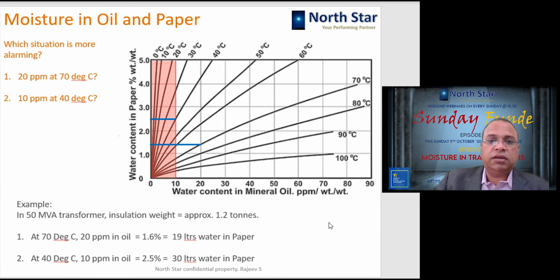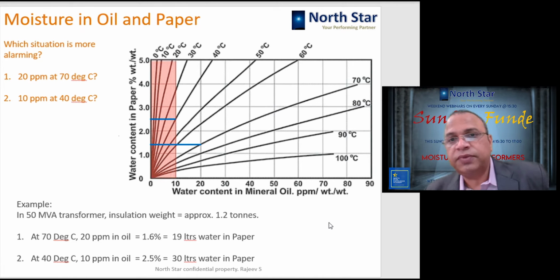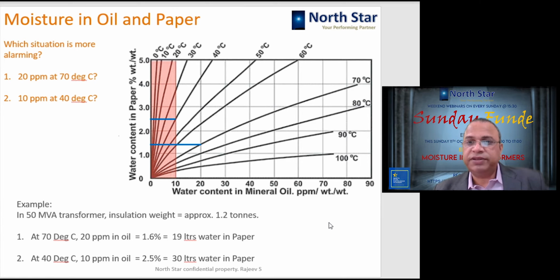Now let us look more into the equilibrium of moisture in the oil. Here you can see several graph lines at different temperatures. These are the temperatures of that particular transformer, from 0 degrees to 10, 20, 30, 40, 60, 70. Here it is the water content in mineral oil in ppm weight by weight, and here it is the percentage in the paper weight by weight. So this is in percentage and this is in ppm.